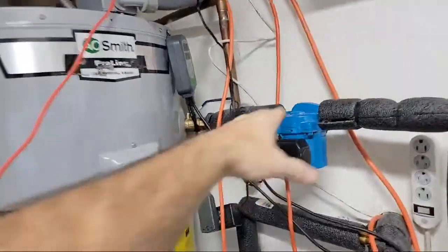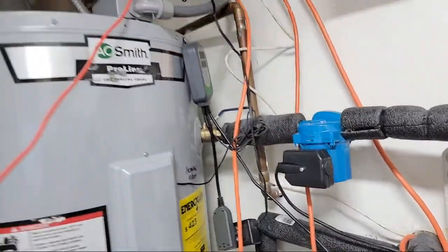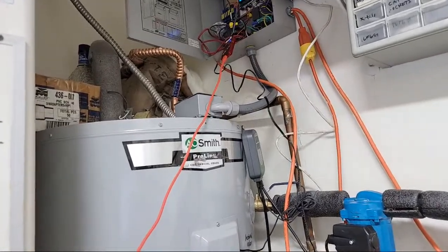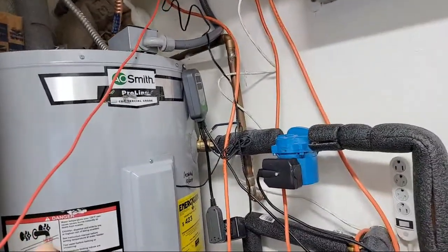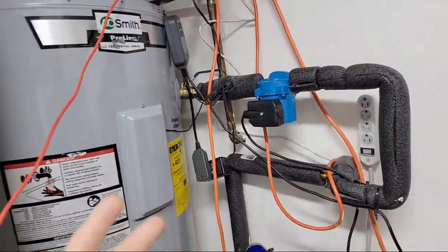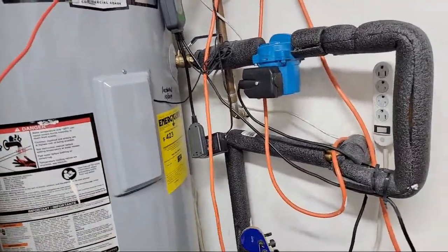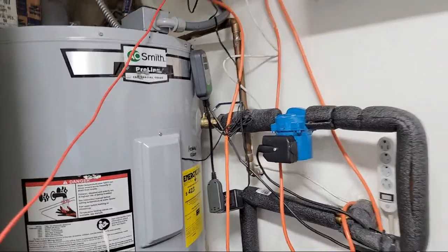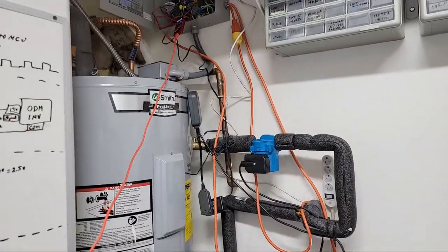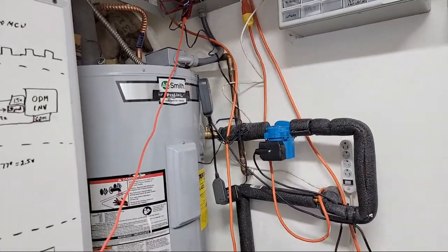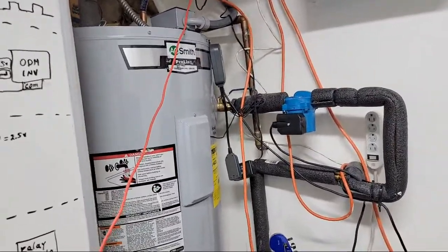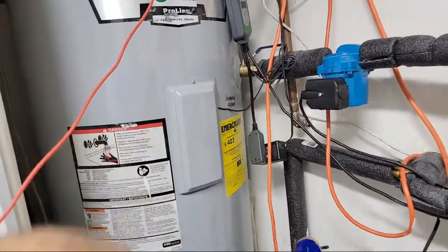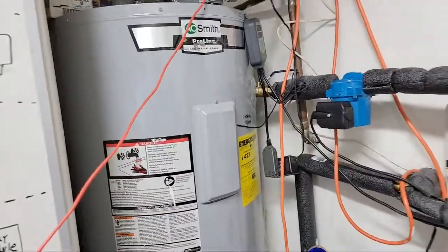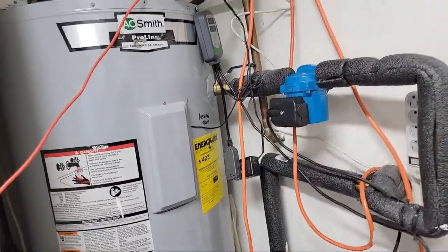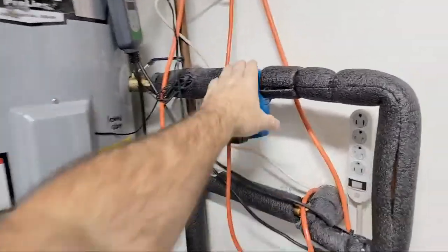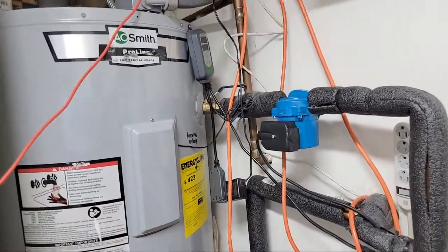I have the pump not even turn on at all until it hits over 100 degrees on that liquid line, and then it kicks the pump on low. Think of a thermostat going on and off on your car, controlling the temperature in your engine through the radiator. And even some boilers do that. They actually have a thermostat in there. That way it pulses the water into its loop, just to maintain a minimum heat rise. So I'm actually doing that by controlling a pump. So it's like controlling the heat rise.